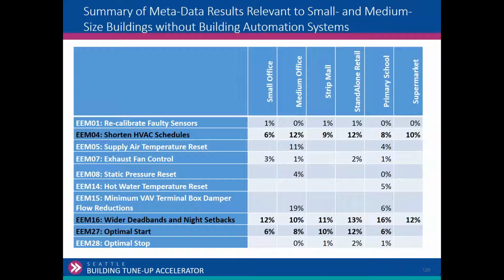Another key for non-building automation systems, so the small to medium, say 50,000 square feet and smaller, were wider deadbands and night setbacks. So increasing the deadband, implementing more of a setback. Setback has always been kind of an issue, and we're going to rely on your judgment depending on the system type. There used to be some basic rules of thumb in light frame construction where you had fairly quick recovery. You could get away with setting back to 55. In mass construction, concrete tilt up, brick, you wouldn't go as far down, maybe 60. But now we're starting to see systems like VRF heat pumps where you do very little setback, and they actually consume less energy because they're running at part load rather than trying to recover after a weekend.